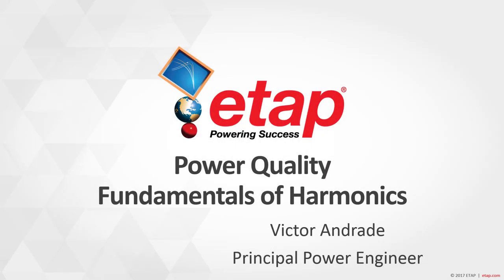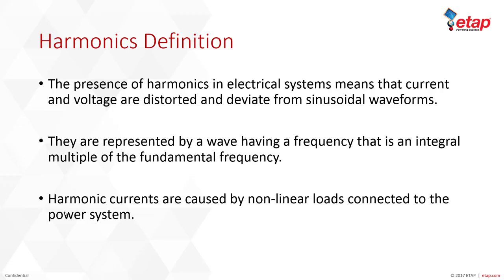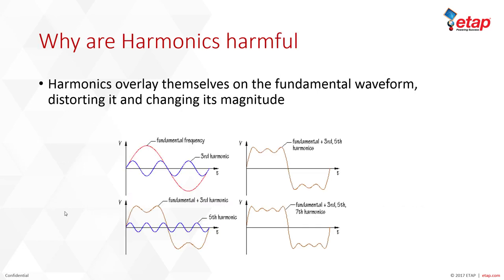This presentation covers fundamentals of harmonics, which falls under the power quality analysis modules. The presence of harmonics in electrical systems means that current and voltage are distorted and deviate from sinusoidal waveforms. They are represented by a wave having a frequency that is an integral multiple of the fundamental frequency. Harmonic currents are caused by nonlinear loads connected to your power system.